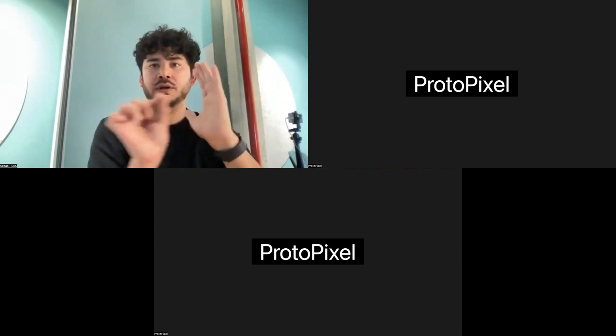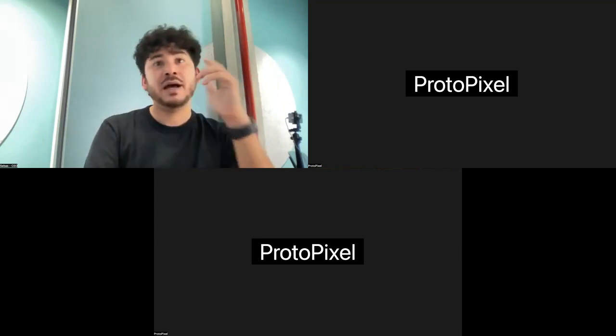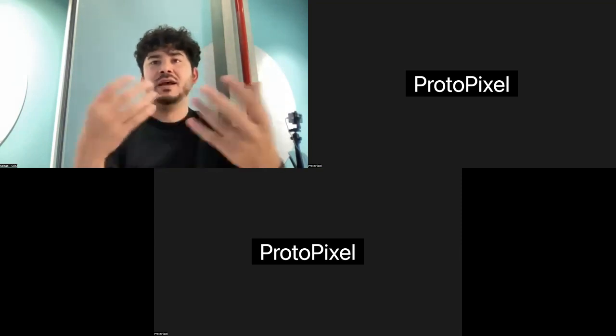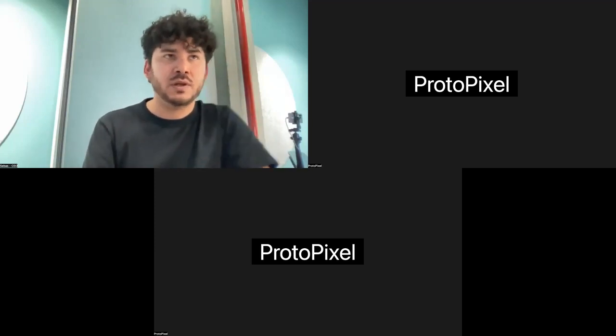So, for example, if you have a DT6 fixture, you will only see the brightness control. But if you have a DT8 with color temperature or something like this, it will detect that it has color temperature, and you will be able to have the brightness as well.